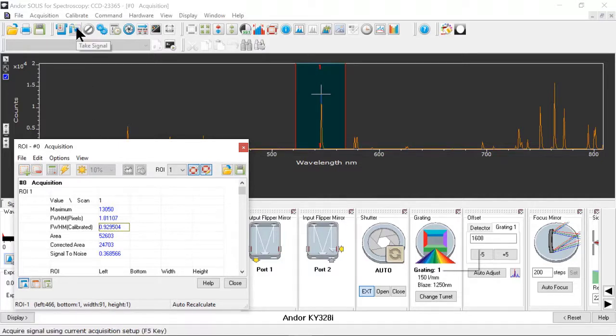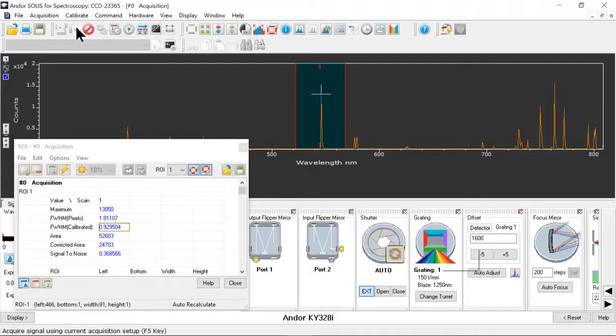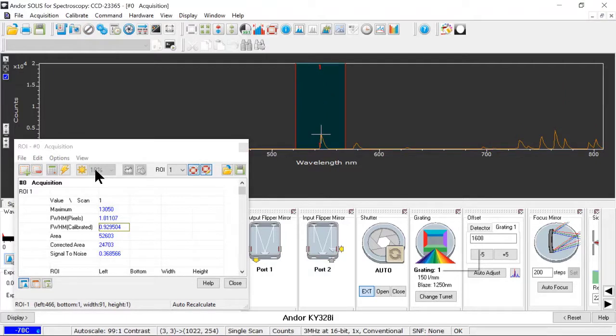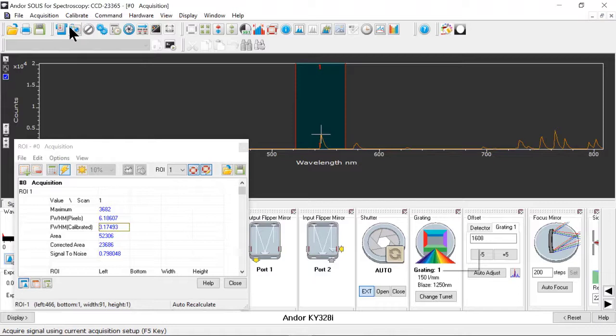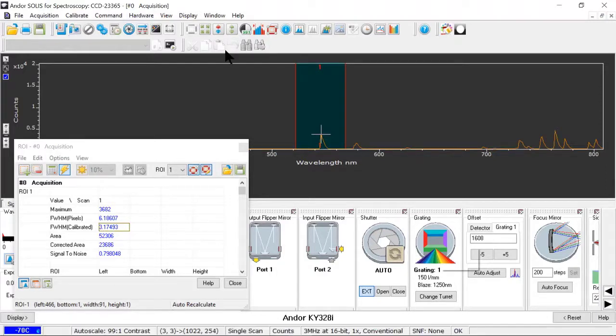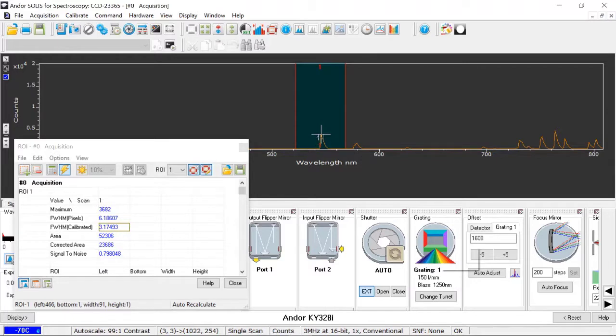If I redo this with my focus that I've purposely moved off, you can see that changes quite a bit. And if I set this to update, you can see now my resolution has dropped quite a bit. My full width half max, which is a proxy for my resolution, that is my ability to separate two closely spaced spectral lines, which I can no longer do here at this doublet, has gotten quite a bit worse.